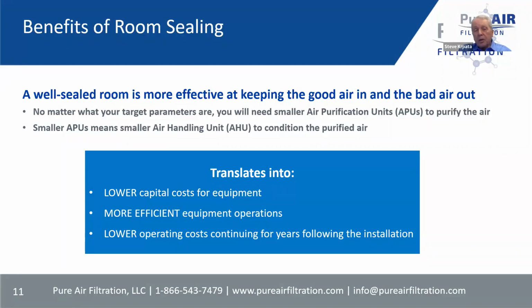Whatever your target parameters are for air quality or room pressure, the better the sealing of the room, the smaller the units you will need to achieve those parameters. That means a lower capital cost for your air purification units, and smaller requirements for any air handling units.